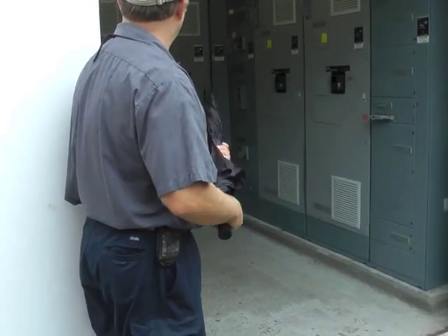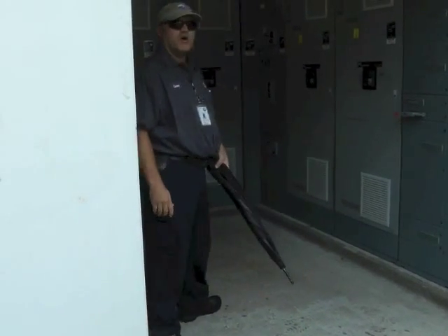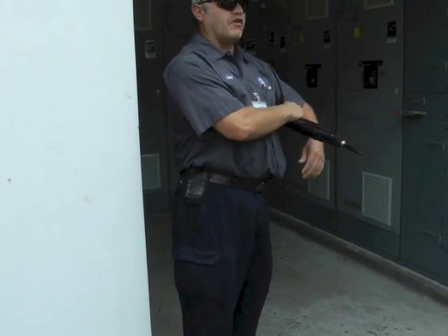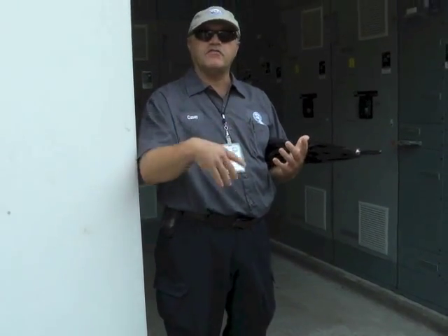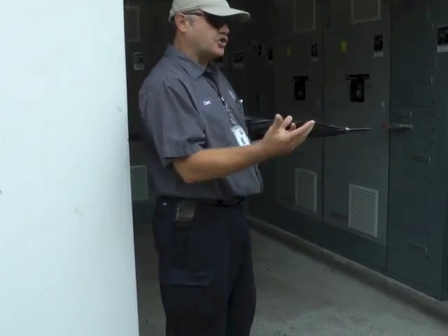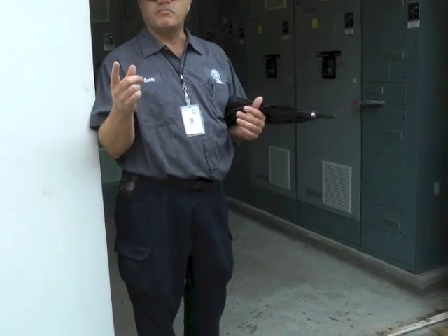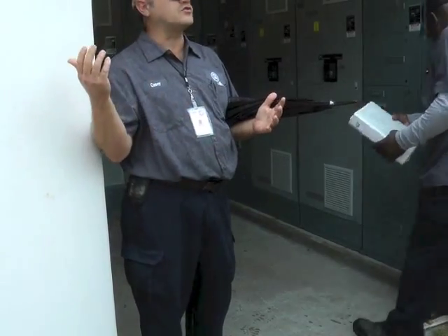But right here they have submersible pumps, like you said, they're 60 horsepower pumps down below. Yes, these drives right here, these four drives, there's one for each pump. And the way they work, depending on the flow, is how fast they run. That saves electricity, not having to run the pumps real fast all the time. And they'll shut off when they're not needed too. Most generally, only one pump out of four is running, because they can handle so much flow.